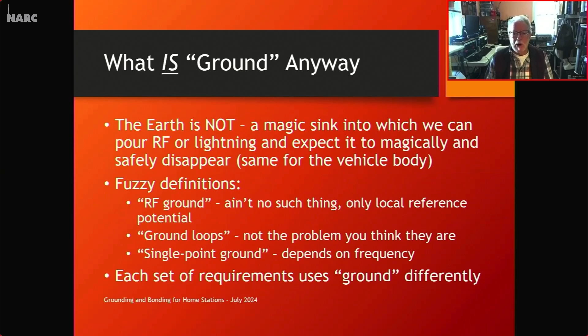So let's jump over to bonding. That's where we use the same word, you and I. It's simply a connection intended to keep two points at the same voltage. If you go look up the definitions, that's what it is. I'm not talking about how I bond. I'm just simply talking about making this connection to keep the two points at the same voltage, so that everything goes up and down together. The idea is to prevent one piece of equipment from being up here while the other one's down here, or vice versa. When you have different voltages between pieces of equipment, that's what causes current flow. And so by minimizing voltage differences, you also minimize destructive current.